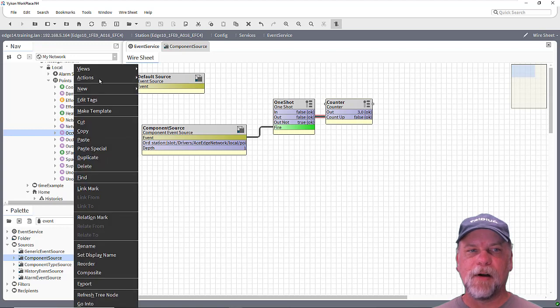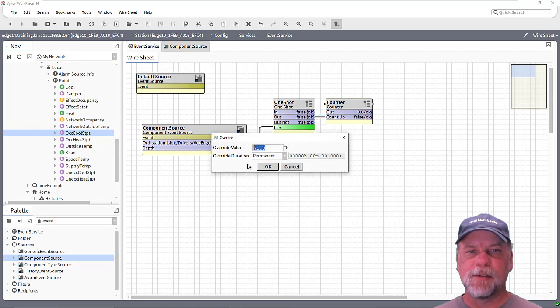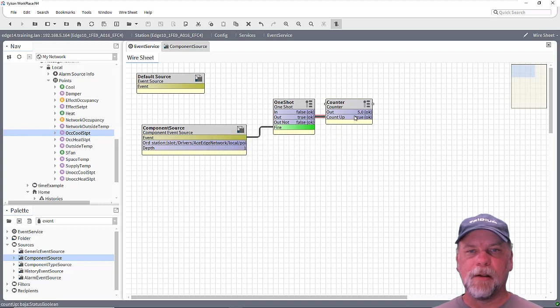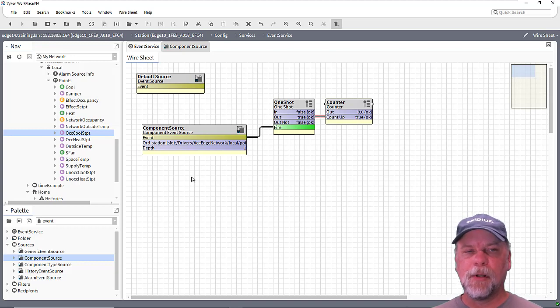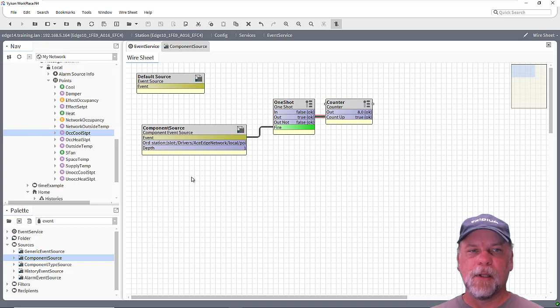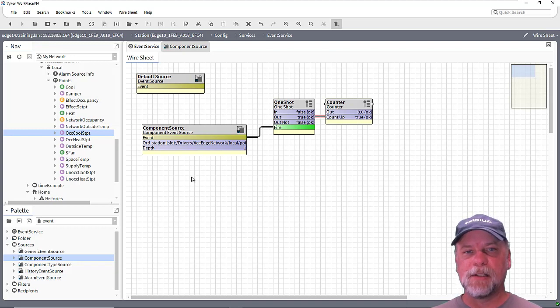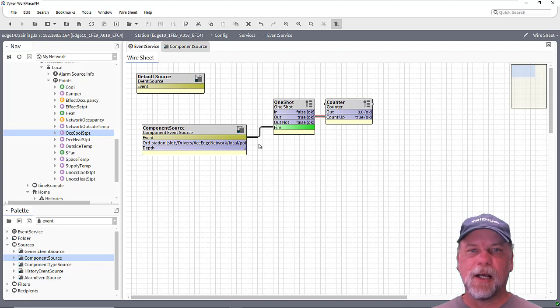And if I do an override, for example, for one minute, then when I invoke that, the counter increments there to five. So it's picking up on any component events, any property change component events — the out slot value changing, the in slot value changing, or the fallback slot changing. It's causing this event topic to fire each time, and then it's incrementing the counter.